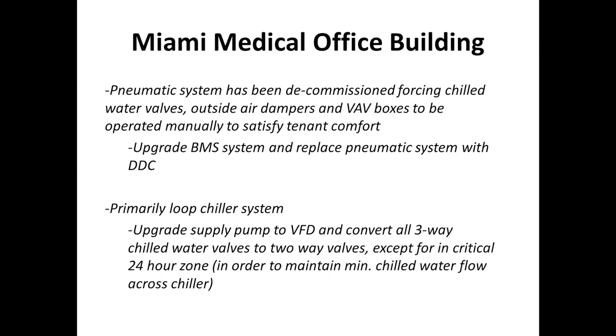We recommended that they upgrade almost all of the three-way valves to two-way valves, which would allow them to install a VFD, a variable frequency drive, on the chill water supply pump. However, we ran into an issue where the chiller had to maintain minimal flow. We were lucky in that this building had one area with 24-hour occupancy. We left three-way valves there so that there was constant flow through that section, which met the minimum flow requirements for the chiller and also allowed us to modulate the amount of chill water that the rest of the units saw throughout the building.